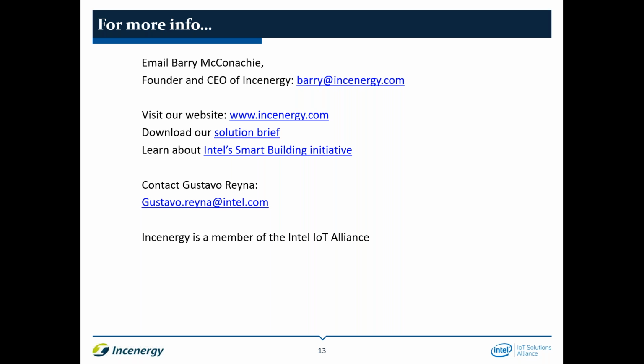I was going to talk a little bit about the specific types of devices. Everything from an HVAC thermostat, which is a fairly simple install by an HVAC technician - low voltage, five or seven wires, replacing the old thermostat with the new one, and it begins communicating. For energy metering, the meter is often placed close to the circuit panel where the breakers are, and we put what's called a CT, a current transducer collar - an open collar that snaps on around the wire - and the meter begins communicating wirelessly back to the platform, bringing the meter data in. In some cases, such as sensors, they can be completely wireless and battery powered - you place the sensor where you want it, and as soon as you turn it on, it begins sending data back to the gateway and up to the cloud.